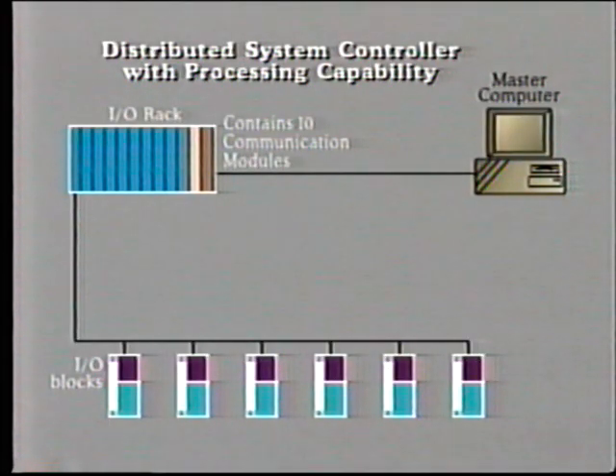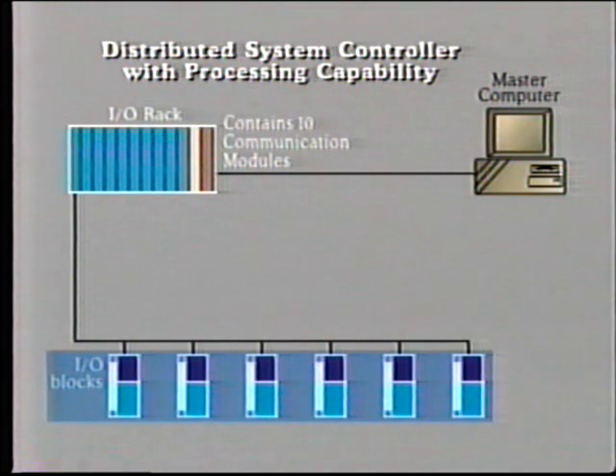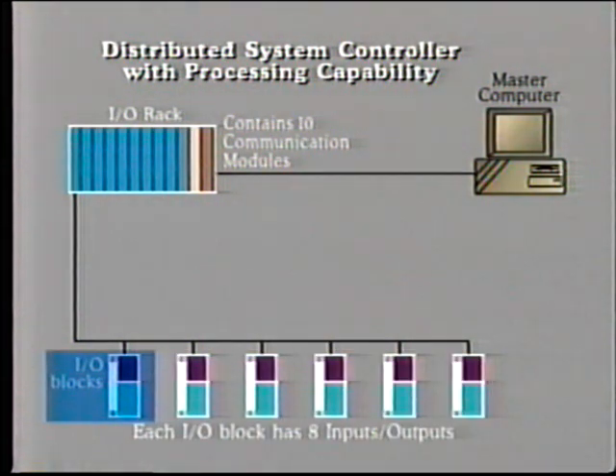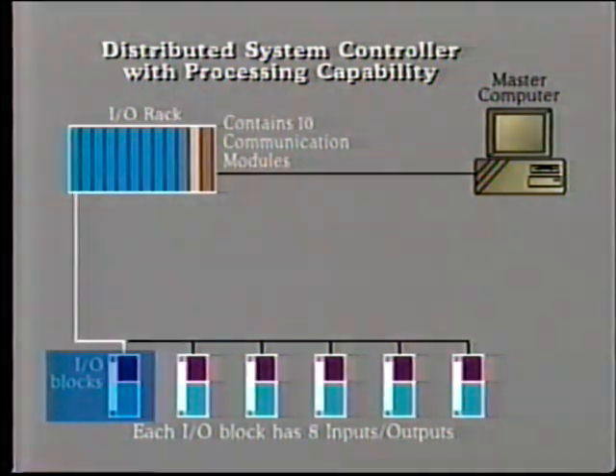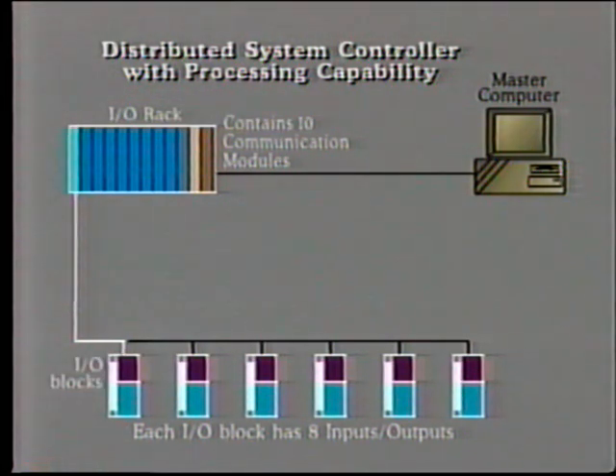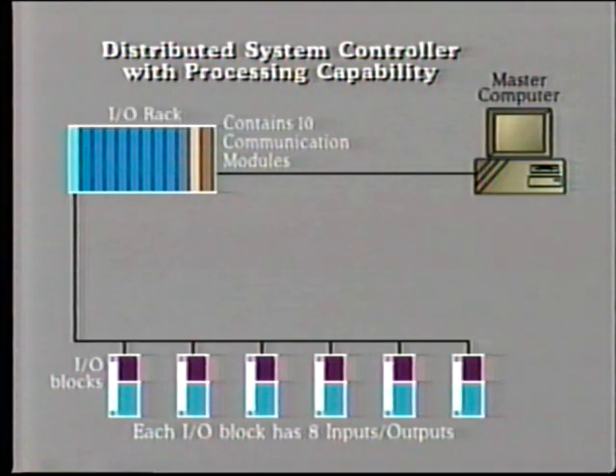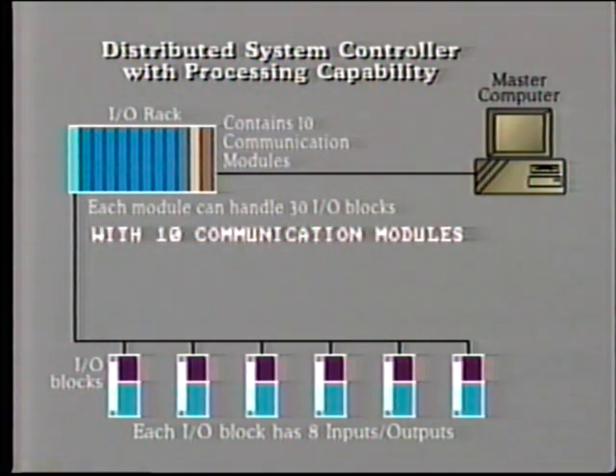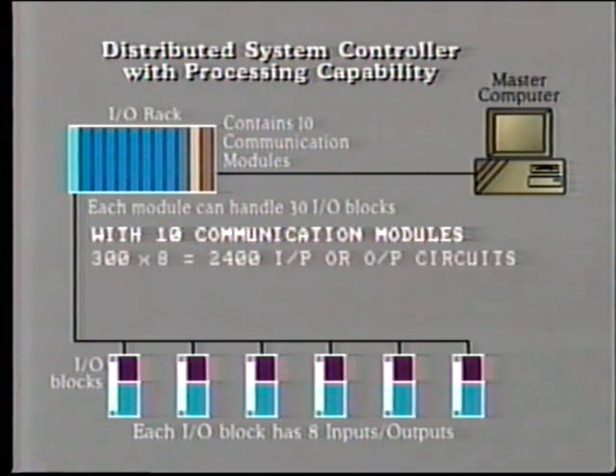One such system that has evolved uses so-called local input-output blocks. The input-output block is usually configured for 8 input or output circuits, and this is connected to a communications controller module, which is plugged into the I/O rack. The communications module can handle up to 30 I/O blocks. So a little bit of arithmetic shows us that with, say, 10 communications modules in a rack, we can connect up to 300 times 8 equals 2,400 input or output circuits. And that's just for one I/O rack.